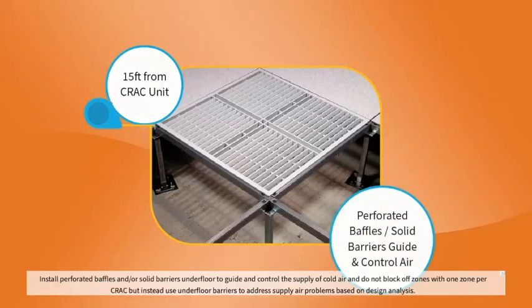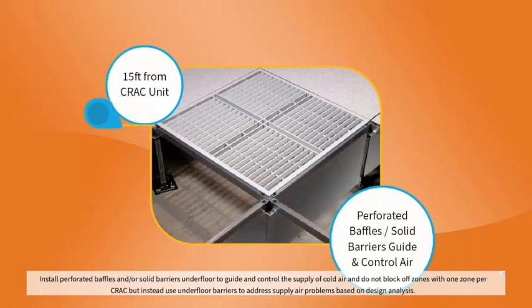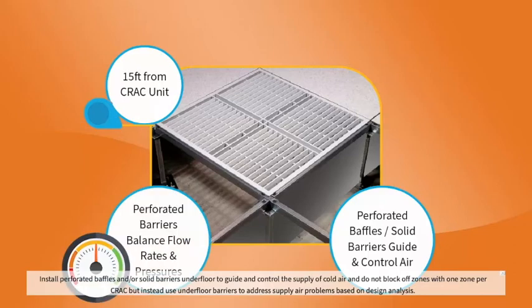Install perforated baffles and/or solid barriers under the floor to guide and control the supply of cold air. Do not block off zones with one zone per CRAC; instead, use underfloor barriers to address supply air problems based on design analysis.